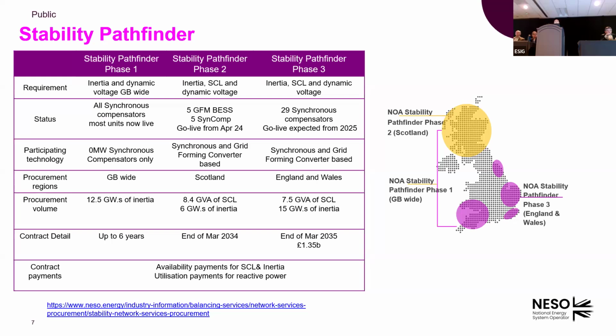We've been running through three stages of the Pathfinders: phase 1, phase 2, phase 3. Phase 1 was predominantly based on mature technology, so we chose a lot of synchronous compensators to be connected to the system. Stage 2 is a more interesting one, more relevant to this talk. We have about five projects which are grid forming batteries, and also five projects which are synchronous compensators, connecting to the Scotland area and helping us manage the system stability. Stage 3 is synchronous compensators as well, just because at that time there was not enough transmission capacity to accommodate more battery projects.